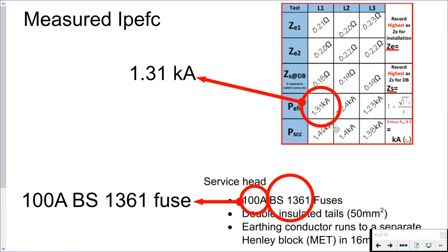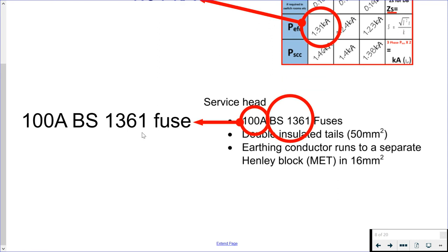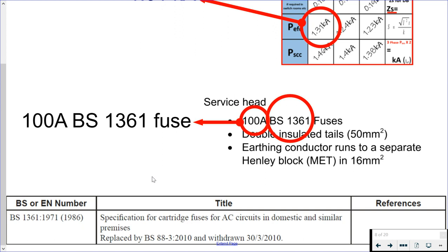Our measured highest prospective earth fault current was 1.31 kilo amps, so that's the I value that we're going to be using. Then we have this information from our inspection: 100 amp BS 1361 fuse. Here's the problem: we've not had a BS 1361 fuse in BS 7671 since the 2011 green amendment of the 17th edition. This British standard number has been withdrawn. If you're going to British standards in appendix one and BS 7671, you'll see that it was replaced in 2010 by a BS88-3 fuse.